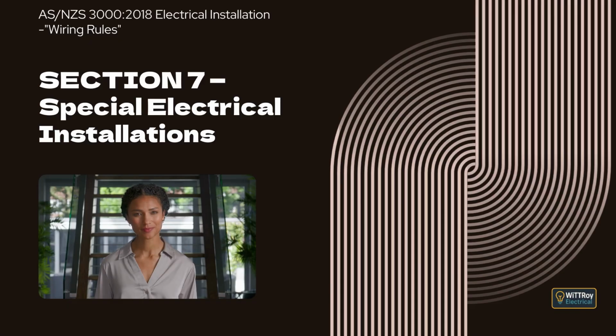Clause 7.4.8.4, Bonding conductor continuity. This clause explains that the resistance of an equipotential bonding conductor for socket outlet earth contacts or exposed conductive parts connected to the same separated circuit must not exceed 0.5 ohms.